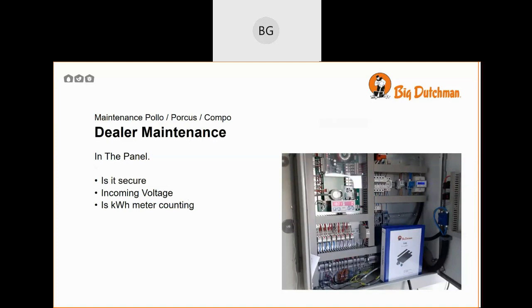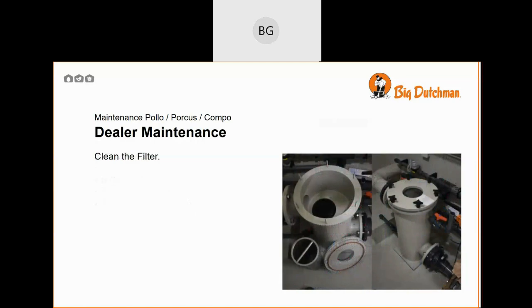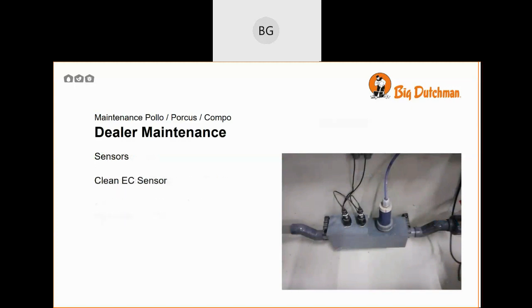In the control panel, we want to make sure the control panel itself is secure, any electrical connections in the control panel are secure, and that the kilowatt hour meter is actually running and recording. Clean the filter, as mentioned in the user maintenance. And for the pH sensors, we will replace and calibrate the pH sensors at 12 months. We will recalibrate every 6 months. Clean the EC sensor. It's also a good idea to retest with your 140 millisiemens test fluid to ensure that it is still working as intended.